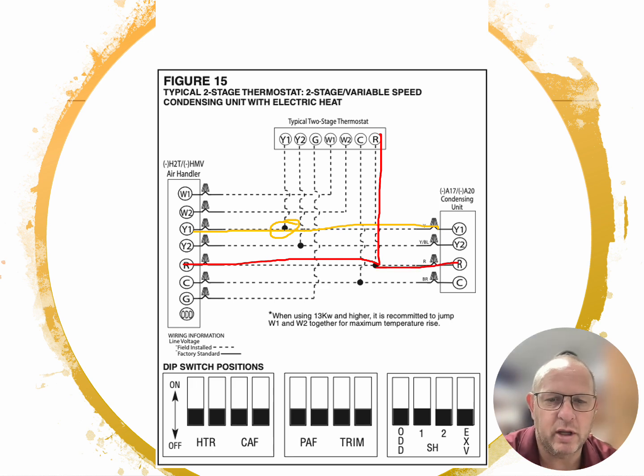The R does not turn on the compressor or the outdoor fan. And I need you to understand that. There must be a board on the outdoor unit on this one that requires 24-volt power to operate, either for a safety or other means of operation. But we're getting all that 24 volts from our indoor unit. And that's coming to it from the R terminal. The next thing the thermostat's going to do, it's going to say, hey, we need cooling. The first stage cooling will be energized. It will send 24 volts to the indoor unit from the thermostat, and then it will send 24 volts to the outdoor unit. This will turn on the indoor fan, and it will also turn on the outdoor unit.